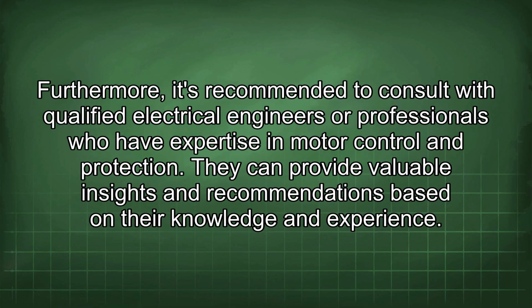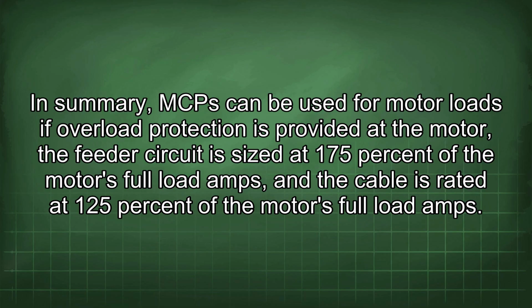Furthermore, it's recommended to consult with qualified electrical engineers or professionals who have expertise in motor control and protection. They can provide valuable insights and recommendations based on their knowledge and experience. In summary, MCP can be used for motor loads if overload protection is provided at the motor. The feeder circuit is sized at 175% of the motor's full load amps, and the cable is rated at 125% of the motor's full load amps.